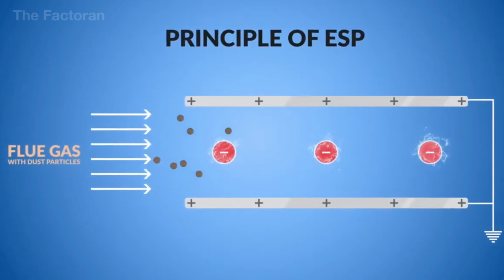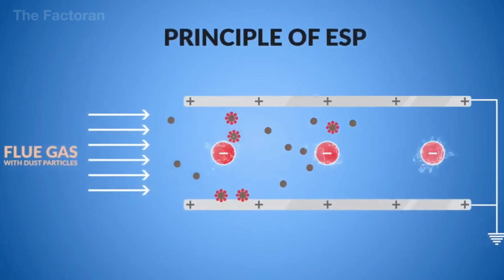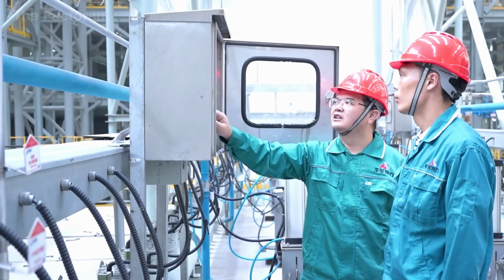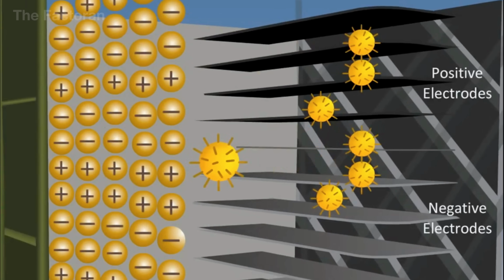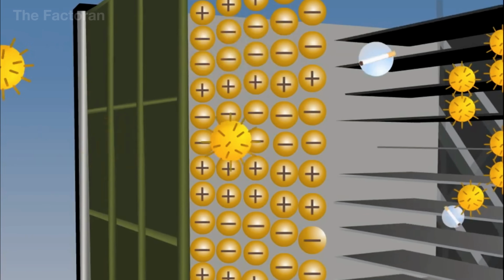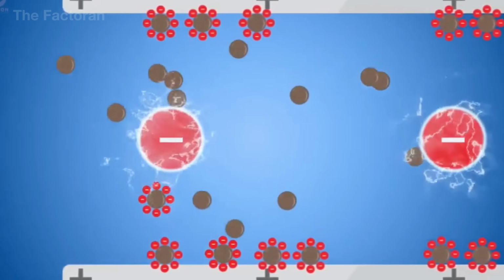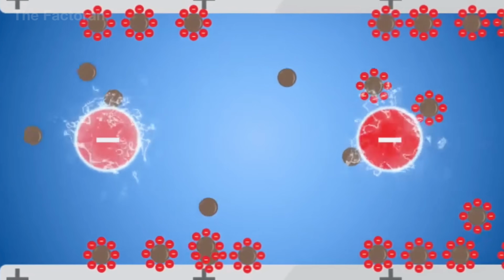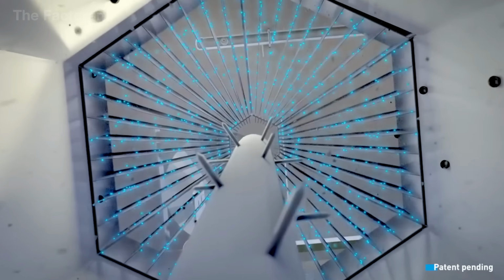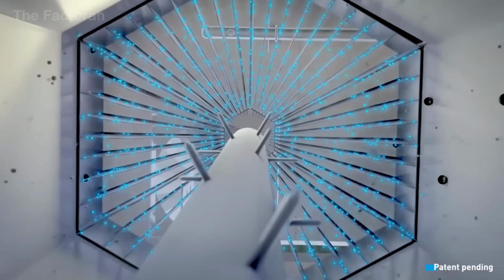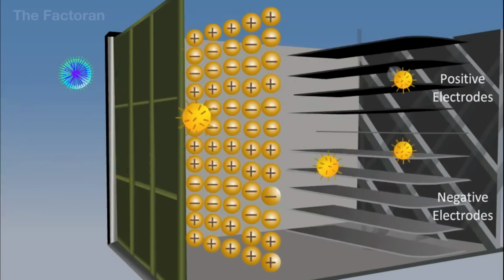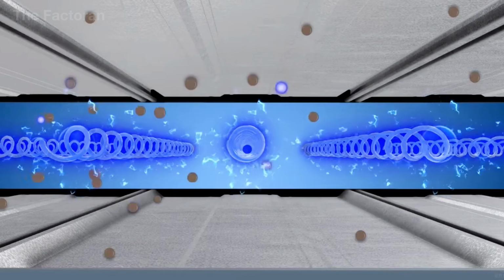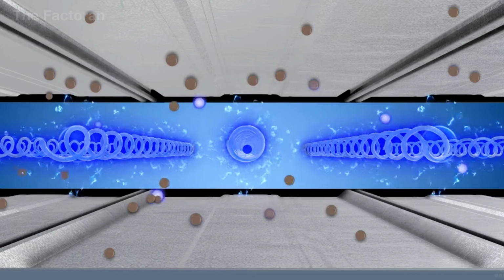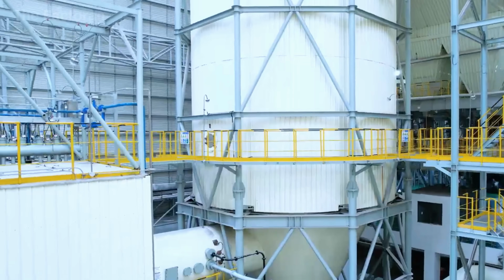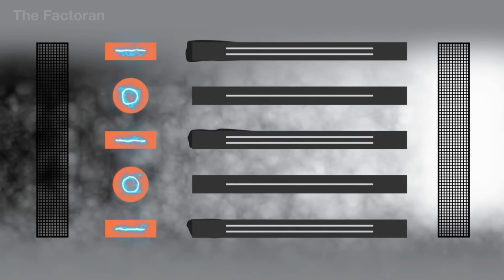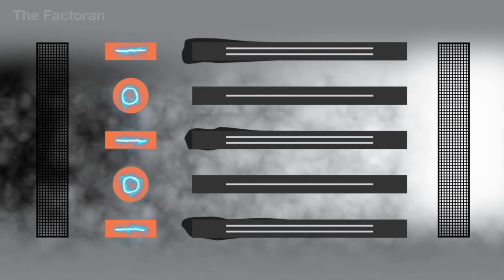Inside the unit, the gas passes through discharge electrodes and collection plates arranged in parallel. When a high-voltage direct current of 20 to 70 kilovolts is applied, the discharge electrodes generate a corona discharge that ionizes the surrounding air, transforming neutral gas molecules into positive and negative ions. These ions attach themselves to the suspended dust particles, giving them an electrical charge. Under the influence of the electric field, the charged particles migrate toward the oppositely charged collection plates. Upon contact, they adhere to the plate surface and gradually form a thin dust layer.